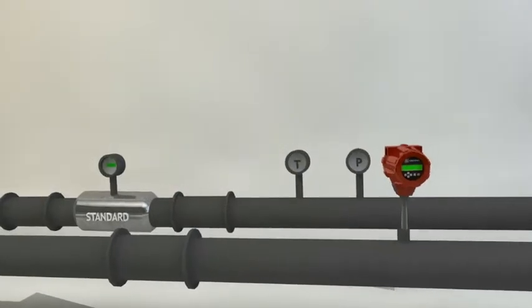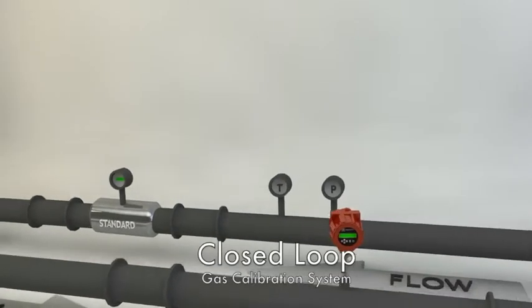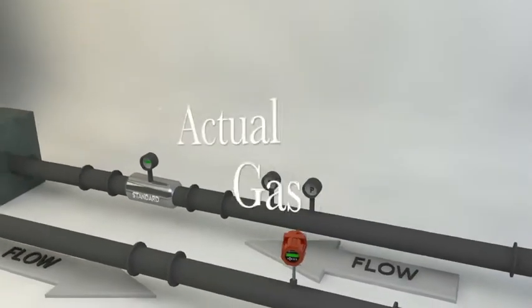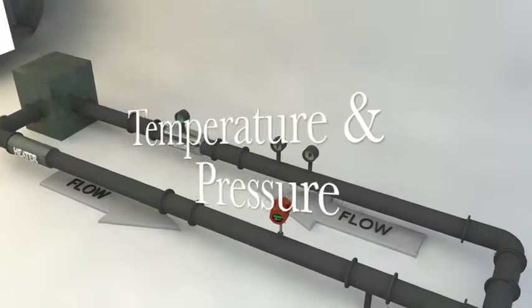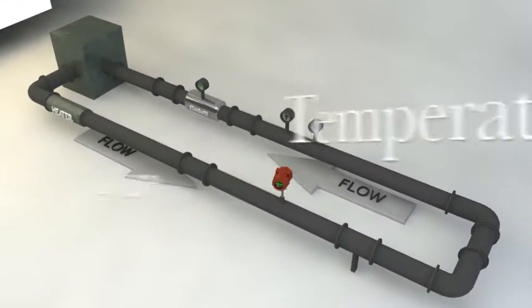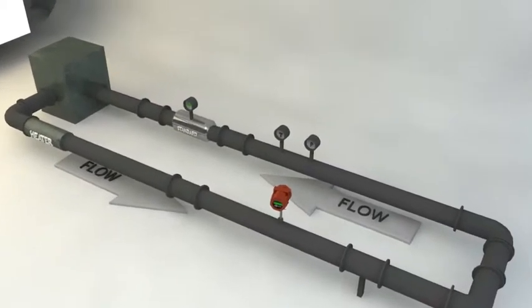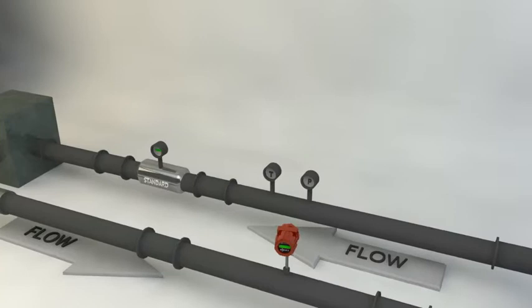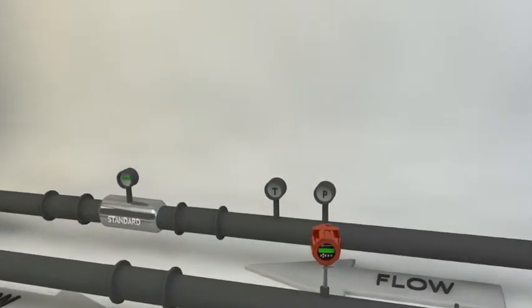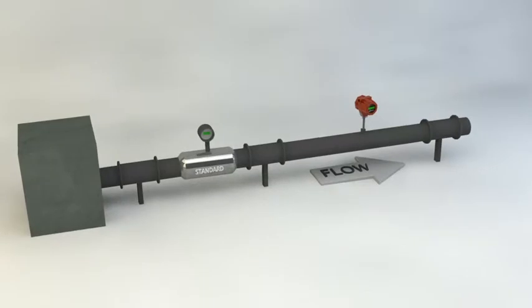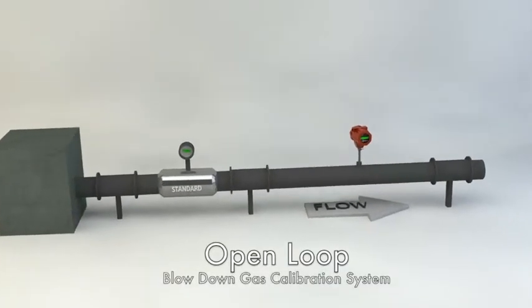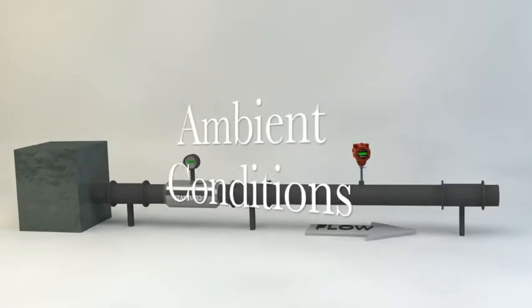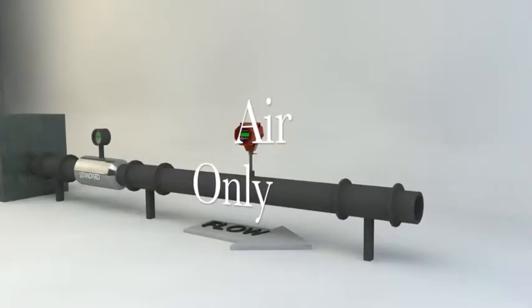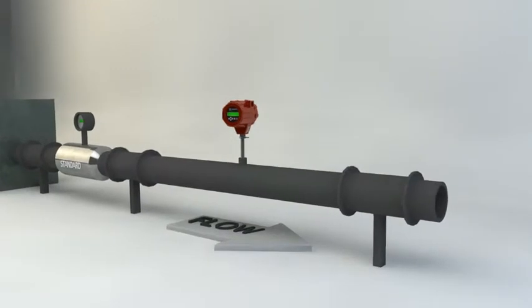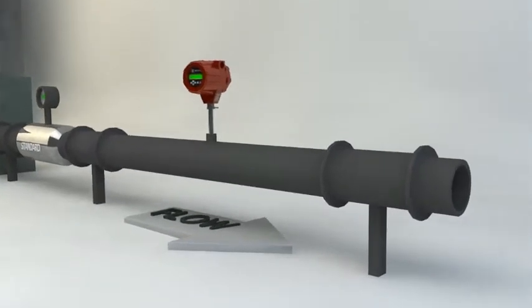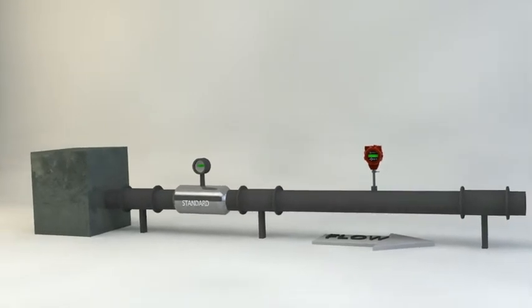Sierra Instruments uses a state-of-the-art NIST traceable closed-loop gas calibration system that is charged with the actual gas to be measured and set to the actual temperature and pressure of the end-user application. This perfectly simulates the customer application environment for a quality calibration, assuring the highest possible performance in the field. Be careful of blowdown or open-loop calibrations, as they operate at ambient conditions and are only done on air. As a result, any other application environment will be inferred indirectly, introducing uncertainty, and thus produce a less accurate meter.